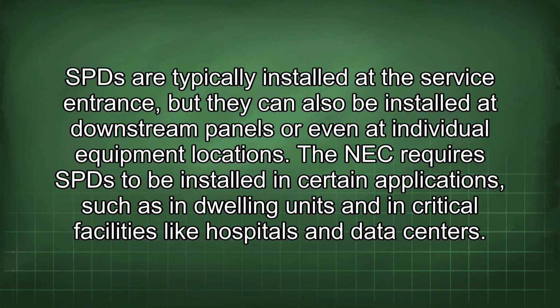SPD are typically installed at the service entrance, but they can also be installed at downstream panels or even at individual equipment locations. The NEC requires SPD to be installed in certain applications, such as in dwelling units and in critical facilities like hospitals and data centers.